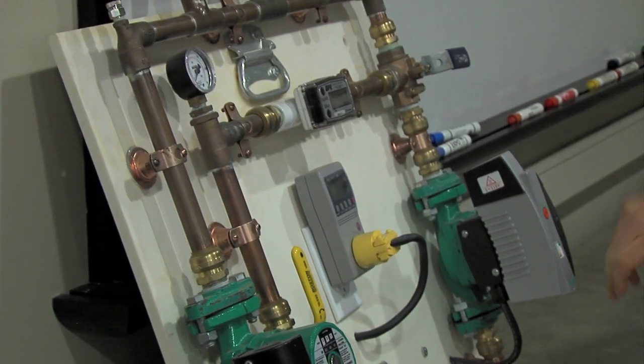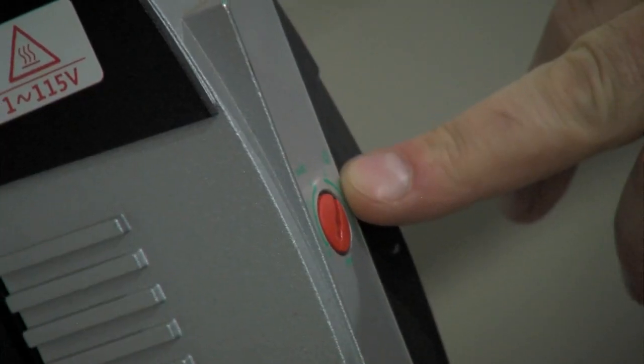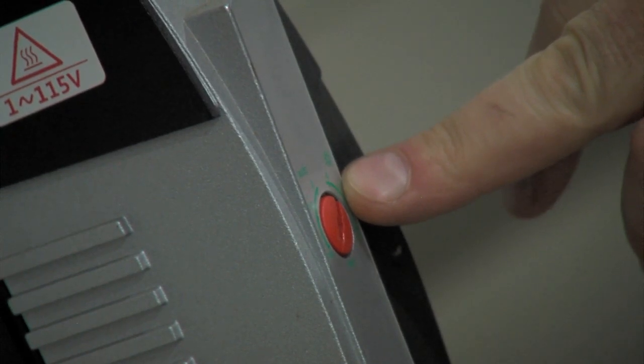Now let's go back to our worst day of the year, which was 60 watts, and switch over to this pump doing the exact same work. It's going to speed up and then slow down. What I'm setting over here is differential pressure, and whoever's engineering the system will decide what that is. They look at the flow requirement and at all the piping and the friction as the water moves around, and work out how much differential pressure I have to create to circulate around this worst circuit. Once that's figured out, it's set here.